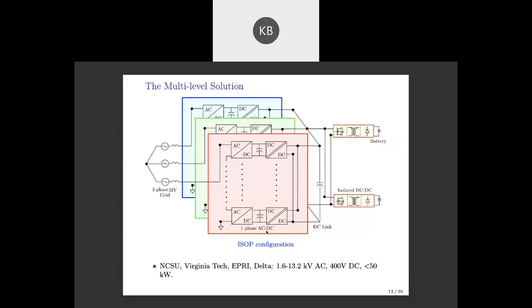So you not only series all the DC in the same phase, you can also series the DCs coming out from each phase across all three phases to make a common DC link, and then connect your chargers with isolated DC-DC converters to the batteries. This is basically the idea, and a lot of universities and companies have implemented this.